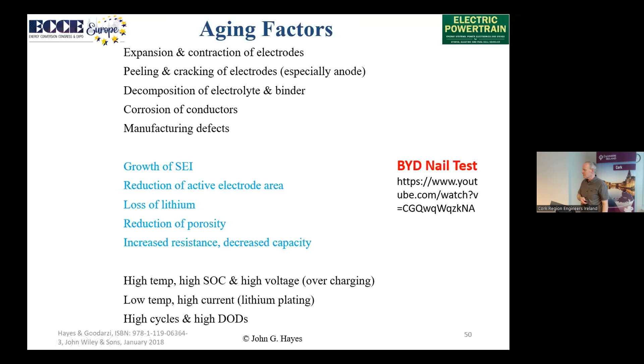So with thermal runaway, what happens? Our pack is designed to operate roughly between minus 30 and plus 60 degrees - though it's not great at minus 30. What happens at about 90 to 100 degrees, or maybe lower, is the solid electrolyte interface, that lithium barrier layer along the anode, breaks down.